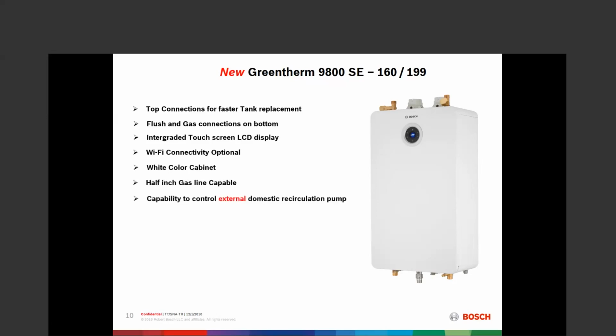And we can also use it to drive an external domestic recirculation pump. Driving the external domestic recirculation pump allows the unit to control the flow of water for domestic recirculation. UEF up to 0.96, and as an advantage for the contractor, ease of installation in the field. On 2-inch PVC, solid non-foam core PVC, we can push the exhaust up to 60 feet.